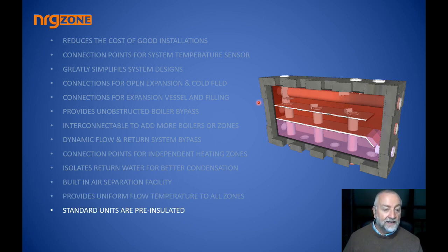And then the last thing I didn't mention is that standard units come with 25mm thick high density insulation, and if the pipe connected to the manifold is as good a quality as that, you're going to have practically zero heat loss where there shouldn't be heat loss, and all your concentrated energy will go where it should go, out to deliver heat to where it's needed, increasing the efficiency of the system again dramatically.